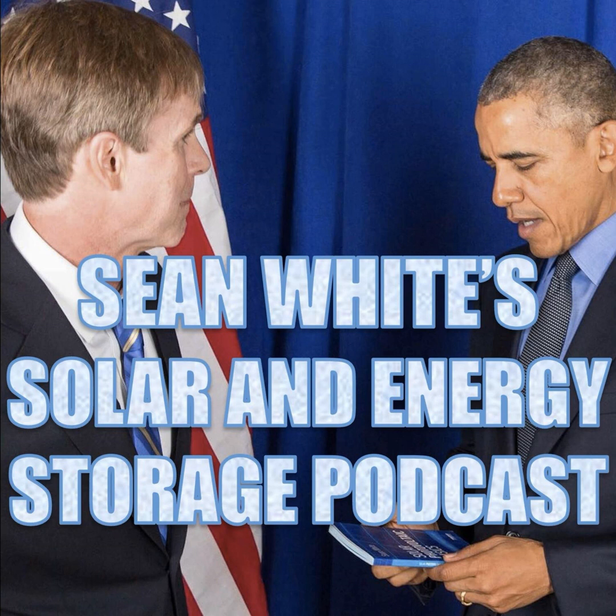So typically, if you're working with an energy storage system, you're not going to be seeing medium voltage unless you're working with a utility scale system and you are connecting to medium voltage transformers. And that can go up to 35,000 volts. A lot of you probably think that's high voltage. In fact, it's kind of interesting when you go to an electrical installation, it's not too uncommon to see people put high voltage next to 480 volts. Just remember, there's different definitions for medium voltage.